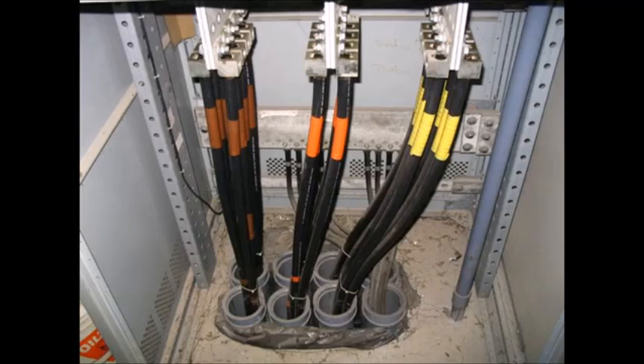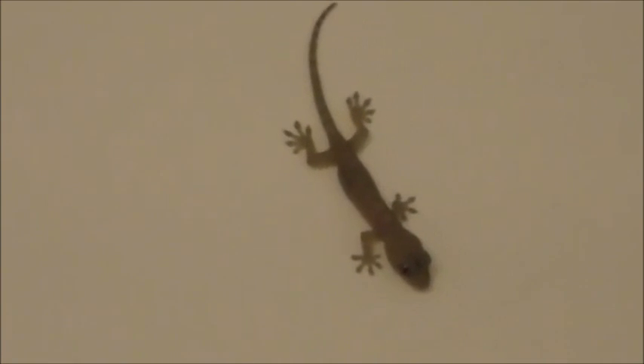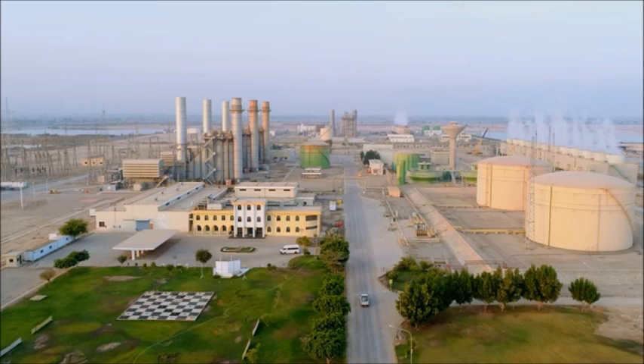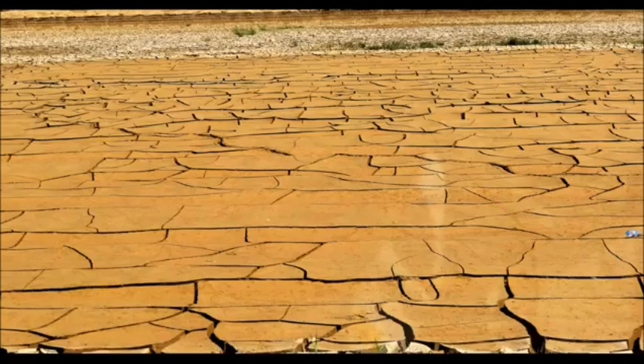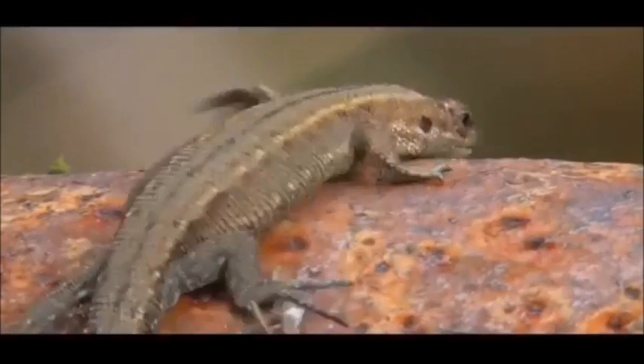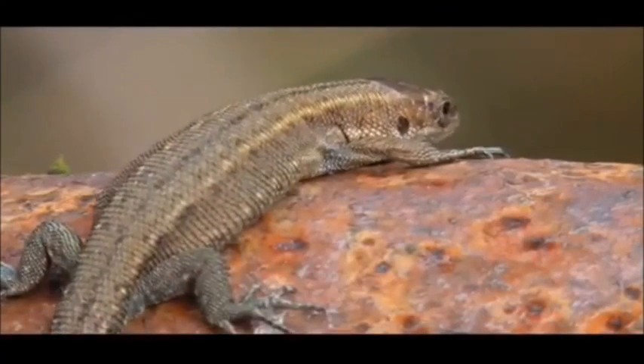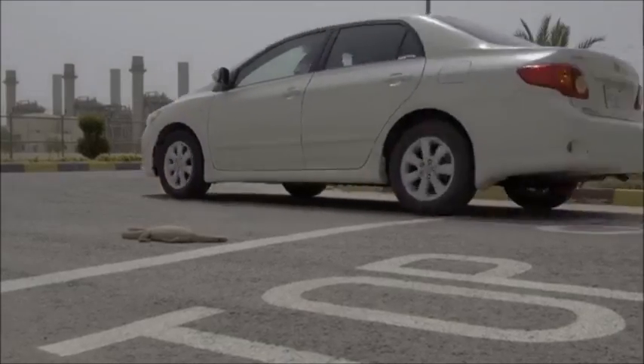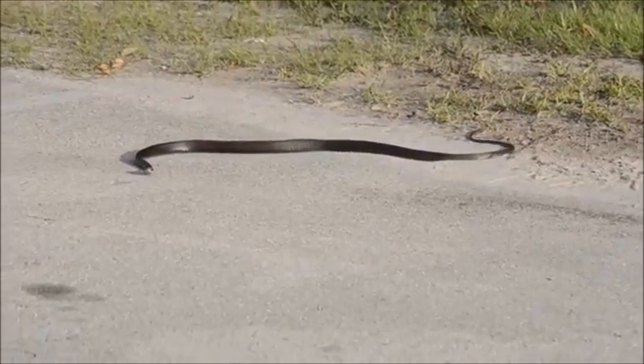Upon a further closer look around, it was observed that there are gaps in the openings of cable conduits and breaker cubicle doors. This provides sufficient space for lizards to ingress. Conclusion and root cause: the UCH power plant is located in a deserted and semi-arid area which inhabits common lizards and wild reptiles and snakes in abundance. It's therefore not possible to completely eradicate these species.